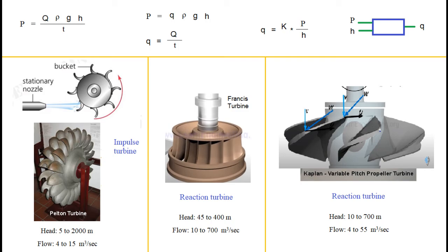In the case of the Francis turbine, water enters tangentially and leaves the turbine axially. These are suitable for medium head and high flow rate of water. Before water reaches the turbine blades, it passes through water guides to control the flow rate of water. Accordingly, Francis turbines are more suitable for energy efficient operation.